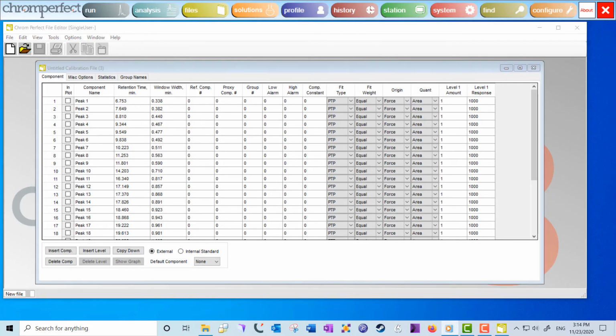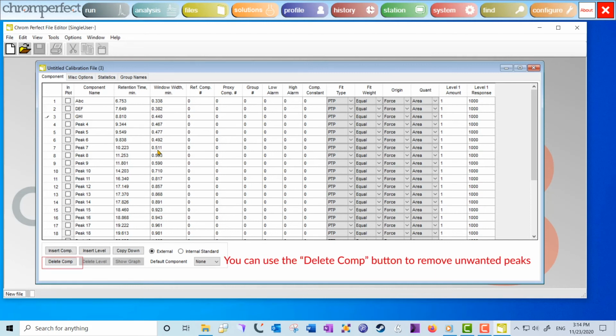A calibration file will be created which has a component for every peak that was integrated, whether it is of interest or not. The names are just Peak 1, Peak 2, and so forth, so you still must type in the correct names. But the expected retention times are filled in, and so are the search window widths, so you have avoided much tedious work. This is a reasonable option for most people.